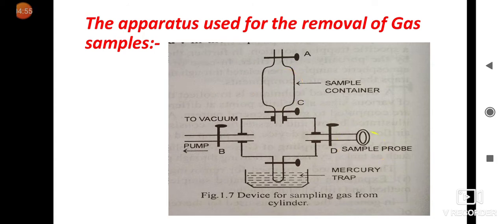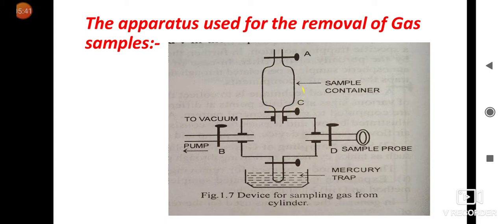This is the sample probe — it is made of a rubber tube, and it will be used to sample from the compressed cylinder or compressed gas. This is the vessel which consists of liquid mercury. It is used to store or trap excess gases coming through this sample probe. This is the vacuum valve, used to clean this sample container connected at part C. The valves are very tightly fitted into this device.